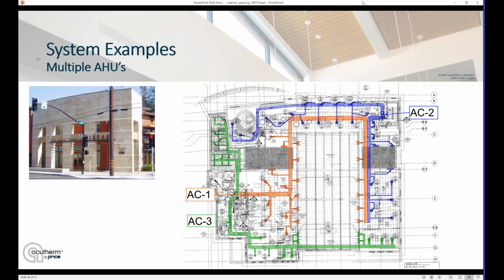Here's an example of a system using multiple air handlers. In this case, it was a smaller library, 3 different RTUs on this particular job. You can see the first rooftop was serving the interior space in orange there. The second rooftop picked up that top and right perimeter of the building, and then the third one was on the left and lower face of the building. So an all low pressure approach, fan speed control here controlling the static pressure amongst the diffusers, and then because it is zoned by separate rooftop unit, no need for reheat. That whole zone goes into heating or cooling as required, with a room temperature sensor providing the decision on when to switch between heating and cooling.